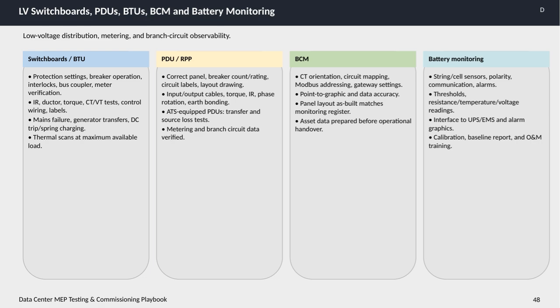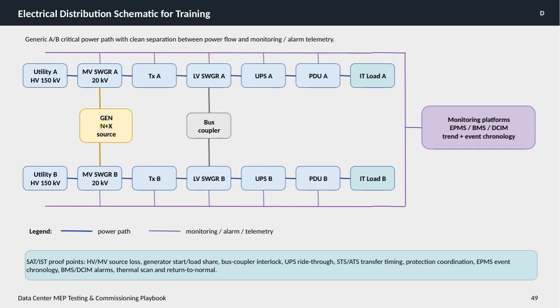data center environment. Here we have a generic A/B critical power distribution schematic designed specifically for data center MEP testing and commissioning. The key concept here is the clean separation between the power flow and the monitoring or alarm telemetry systems. On both sides, Utility A and Utility B provide the high voltage power input at 150 kilovolts, which then steps down through medium voltage switchgear and transformers to low voltage switchgear. From there, uninterruptible power supplies feed the power distribution units, ultimately supplying the IT loads.